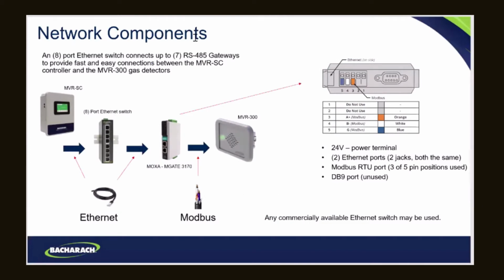Okay, so getting back to the network components, between the controller and the port and our gateway, this is all Ethernet, so it's all Cat5, simple connections. Typically these things have some sort of a wall wart power supply. For the gateway, you'll come in with Ethernet and go out RS-485 to the MVR-300. And the Modbus is typically 2-conductor or 3-conductor twisted pair, 18 to 24 gauge, whatever you want to use with your Modbus cabling. That's power too.